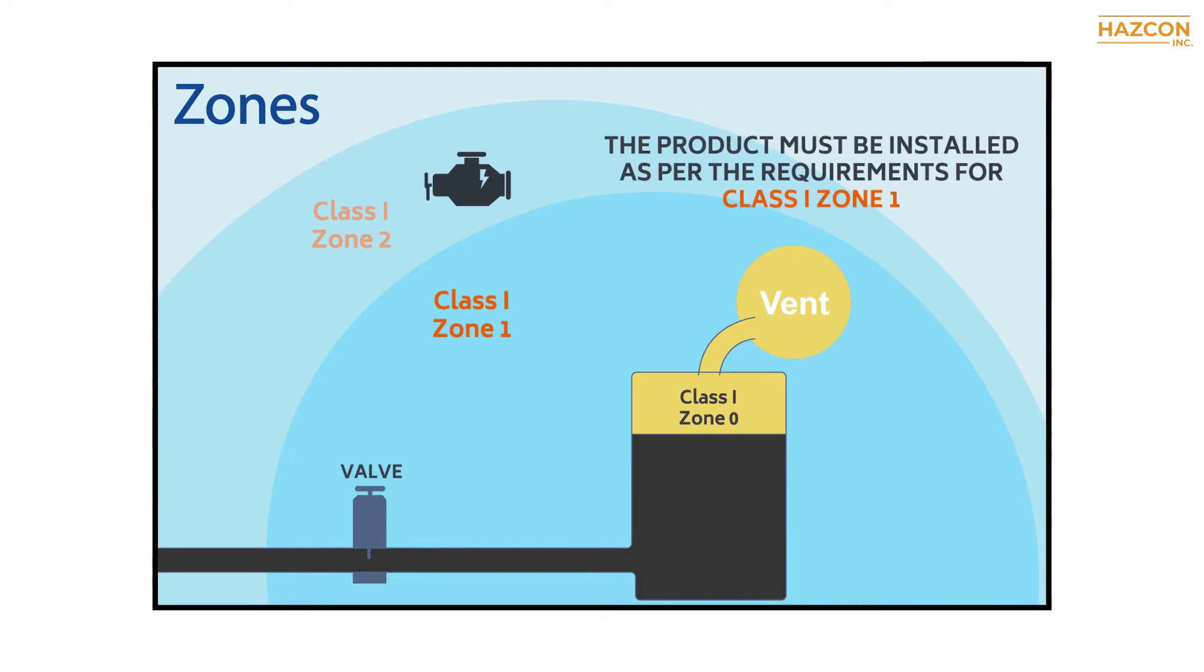We must also note that when products with a higher level of safety are to be installed in a lower level of classified area, it's important to maintain all the field wiring requirements of the original marking, even if the product is installed in a lower level of risk. An example of this is a class 1 zone 1 product, which is permitted to be installed in a class 1 zone 2 location. The product must be installed as per the requirements for class 1 zone 1.